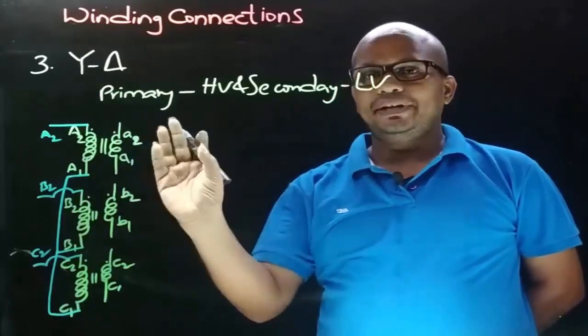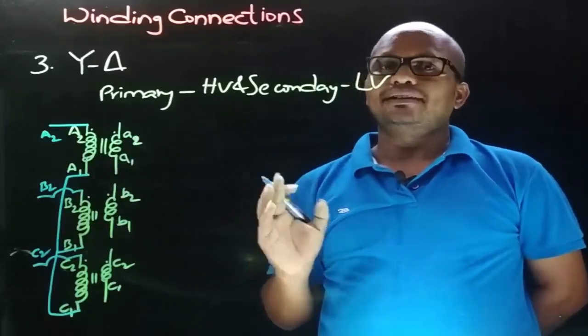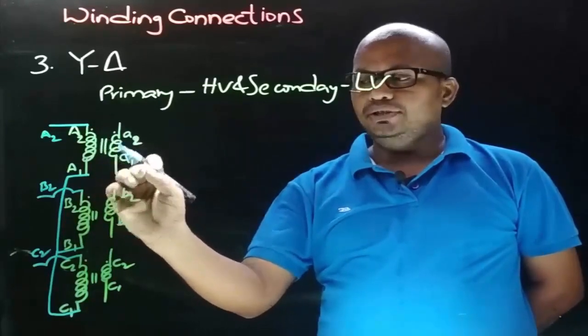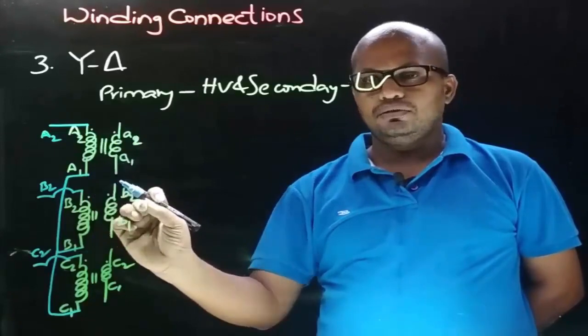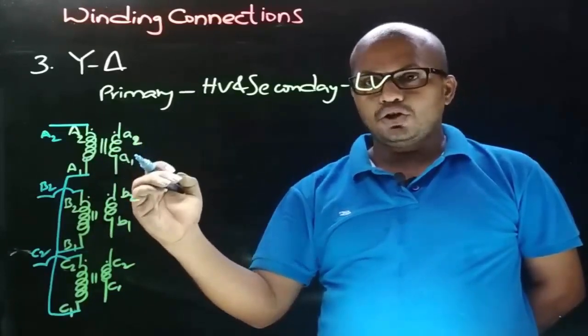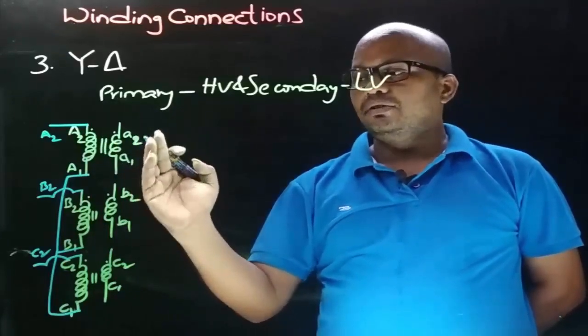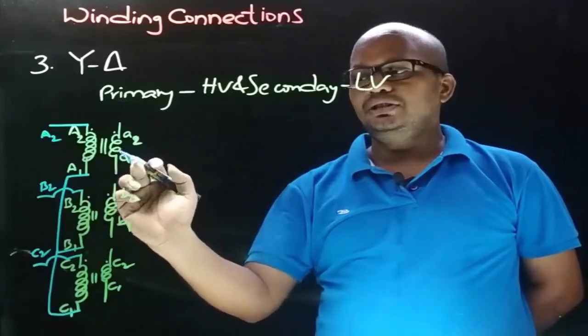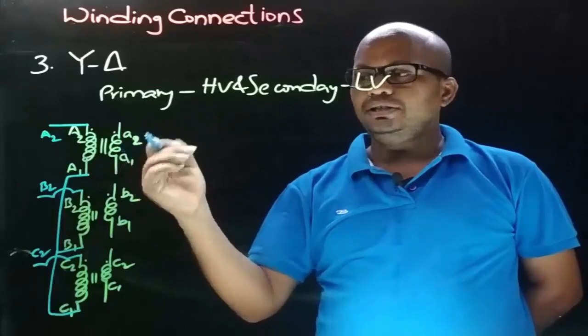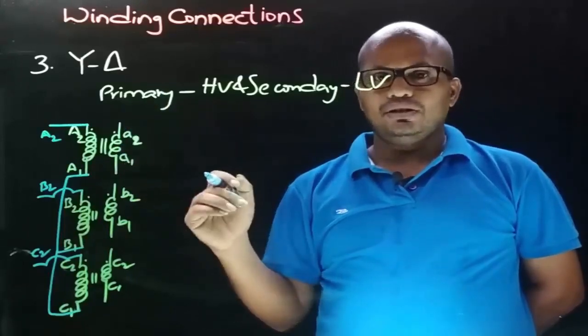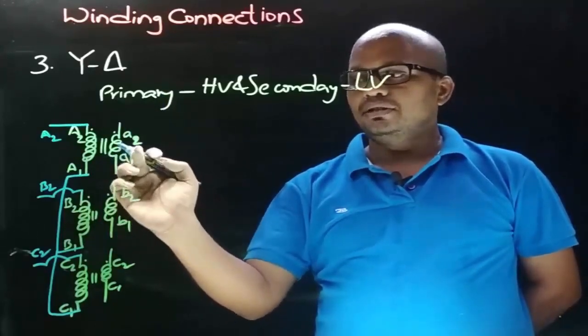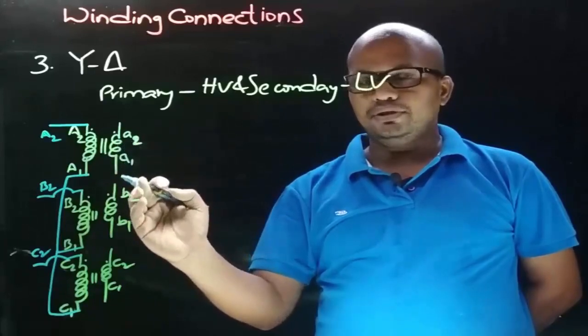Now let's obtain the delta connection on the secondary side. Delta connection is obtained by joining the non-dot end terminal of one coil with the dot end terminal of another coil, or by connecting the dot end terminal of one coil with the non-dot end of another coil. That is, we can obtain delta by joining the finishing end of one coil with the starting end of another coil, or vice versa. Here let's join the non-dot end of one coil with the dot end of another coil.